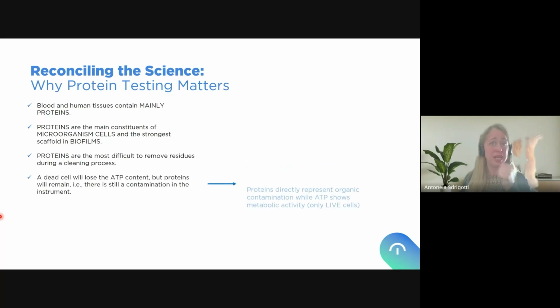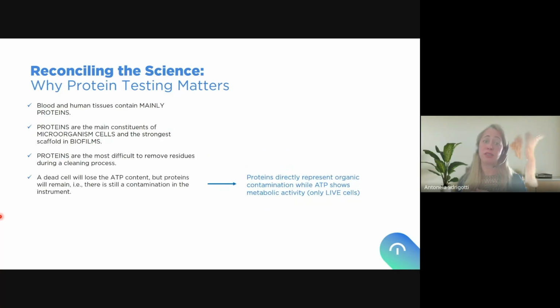A dead cell will lose the ATP content, but proteins will remain, meaning there is still a contamination on the instrument. If I kill a microorganism, but that dead microorganism remains on the surface of the instrument, the contamination will still be there, because proteins will remain and biofilm can form and protection from disinfectants and sterilization will remain. So this is a contamination. So proteins directly represent organic contamination, while ATP shows metabolic activity, meaning only live cells.